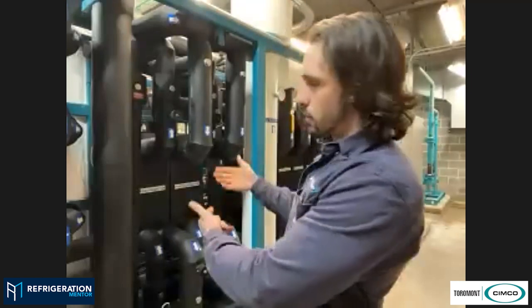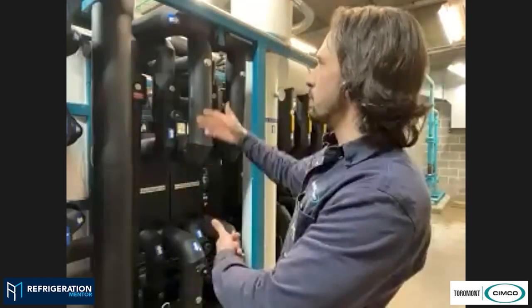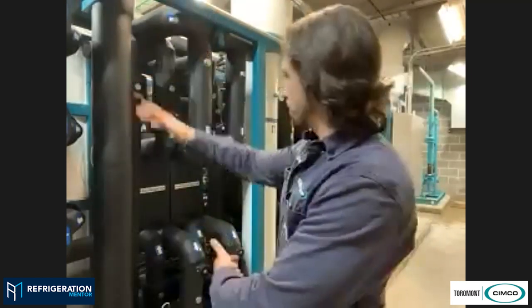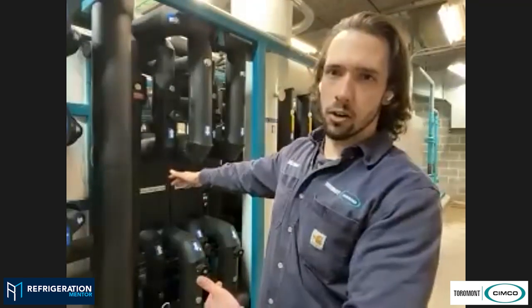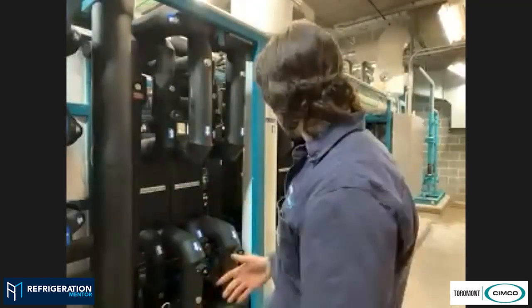To get as cool suction gas back to the compressor rack as possible. But in the event that we need to increase our superheat, that valve closes, directing our flow through the exchanger, and we get that subcooling effect, making sure we have high quality liquid going to our expansion valves. So I believe that answered the question that was asked before.